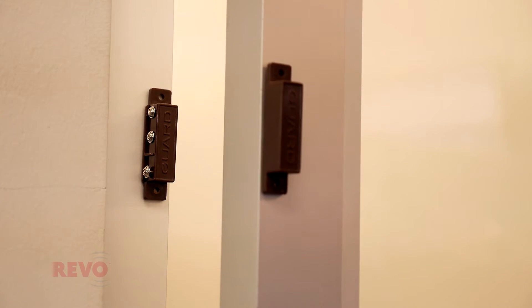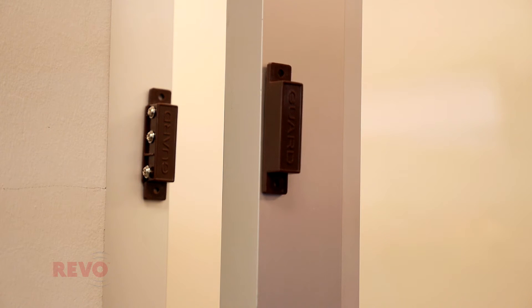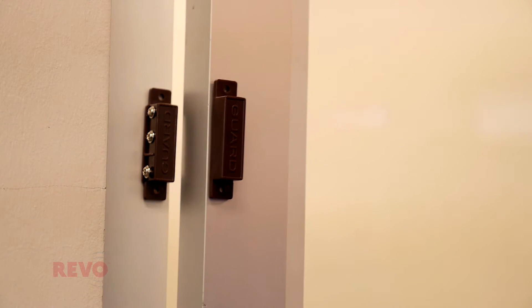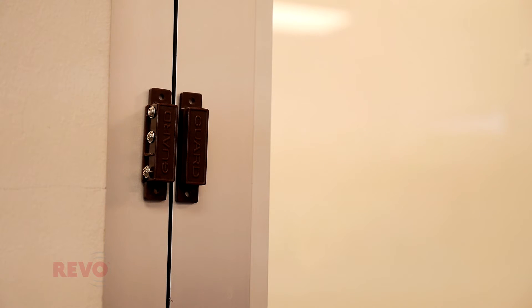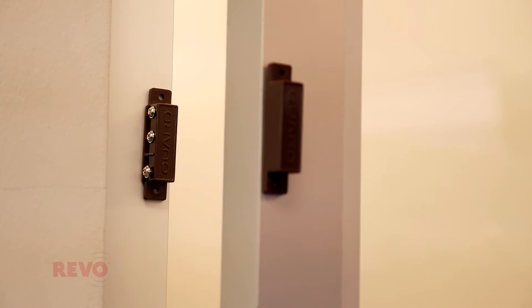NO stands for normally open. A normally open contact will trigger an alarm when the circuit is completed. NC stands for normally closed. A normally closed contact will trigger an alarm when the circuit is broken.